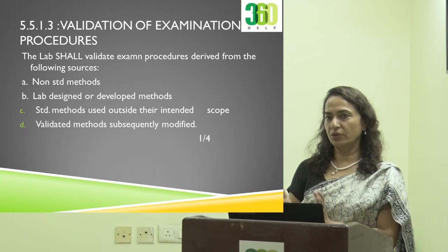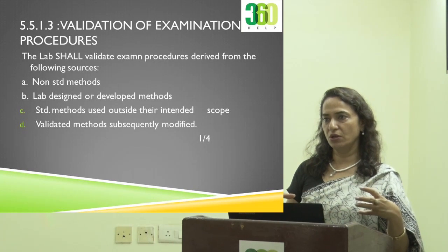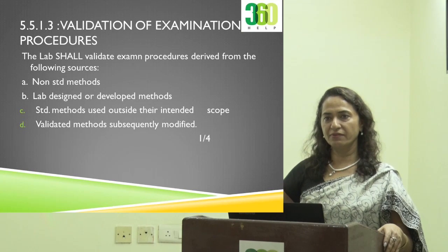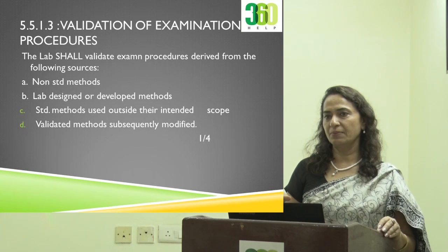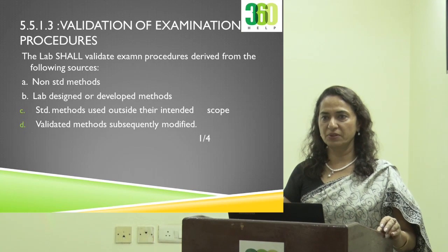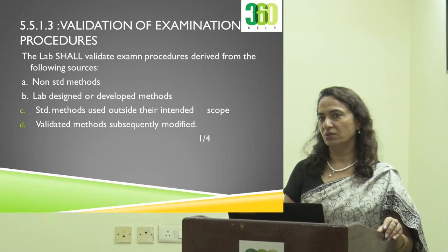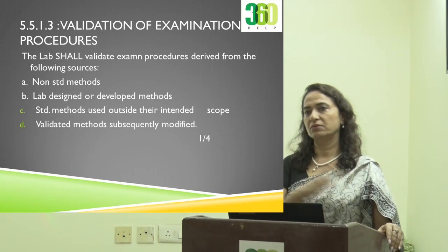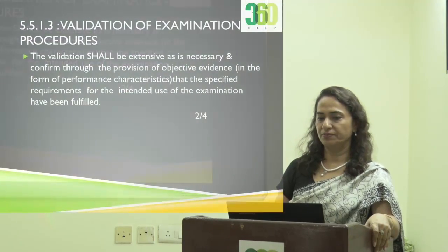Intended use, as I told you, has a range, a linearity, a methodology. If you have to use it for research purposes for higher levels, or a lab doing human samples has to do something on animal samples, where maybe ranges are different, then you will need to validate. Or a validated method but modified subsequently, right? That is where you need validation.